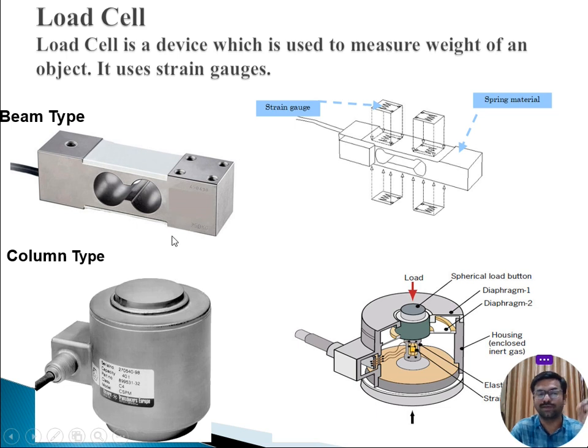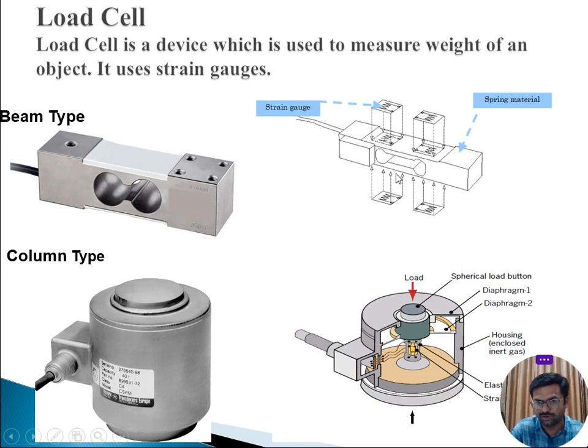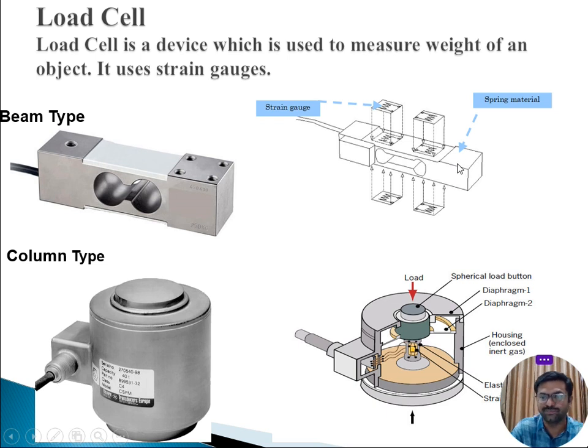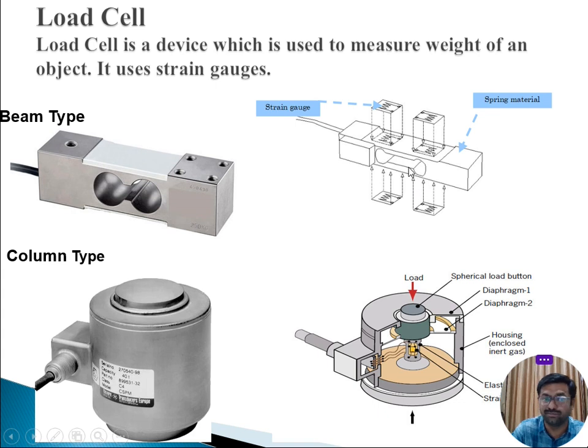In the beam type, you can observe four different strain gauges — the first, second, third, and fourth. Two strain gauges are placed above the hollow tube and two below it. There is a spring material at one end connected to the rigid body, so there is no movement at the fixed end. At the spring end, there is a hanging motion, and that motion is converted into a resistance change, then back to an electrical signal.